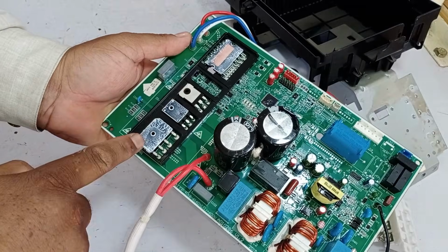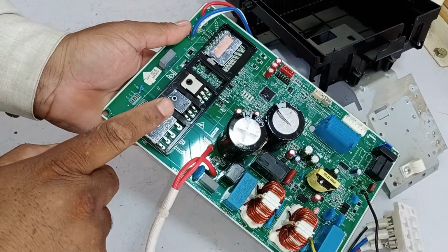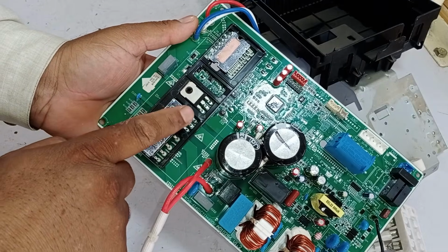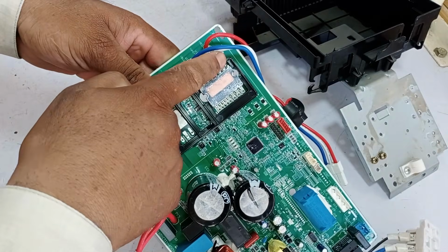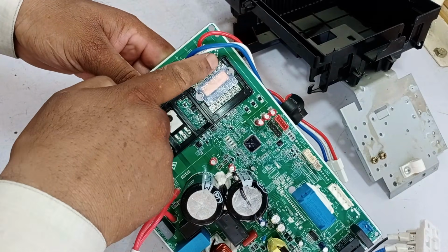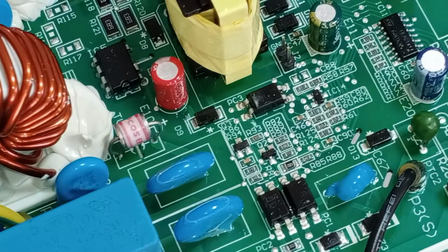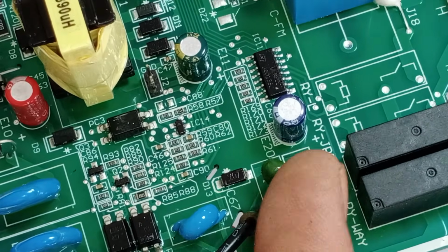Additionally, if the high-side capacitors or the large capacitors fail, the E0 error will occur. If the rectification system, diodes, or IGBTs are damaged, the unit won't work and will show the E0 error. Similarly, if the IPM becomes faulty, especially on the high side, the E0 error will appear. Another possible cause is the communication circuit. If it's damaged, including its components or the small PTC sensor within it, the unit will display the E0 error.